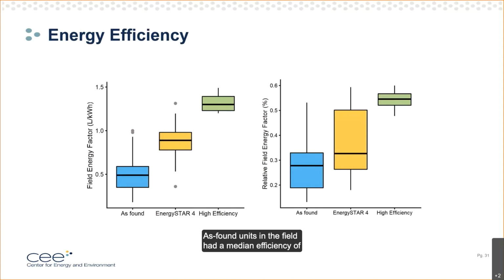So as found units in the field had a median efficiency of 0.5 liters per kilowatt hour. ENERGY STAR 4 units were significantly better at 0.85 liters per kilowatt hour. And high efficiency units remove around 1.35 liters per kilowatt hour. All these values, however, are significantly less than anticipated from the rated performance, as shown on the right, where we've divided our measurements by the rated efficiency levels. You can see that both as found and ENERGY STAR 4 units are performing at about 30% of the rated conditions. The high efficiency units are slightly better, but they're still only performing at about 55% of their rated performance value. So this appears to be very not good, a massive underperformance compared to the rated conditions.